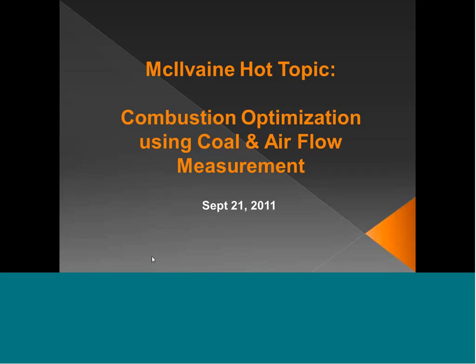Now, the other thing we can do is, if there's a relationship between slip and fineness, if I were to look at the primary air into a pulverizer and compare it to the average velocity, which we calculate automatically on one of our screens in our SCADA system, why can't I convert that into slip? It's possible that we don't need to add any additional hardware if we have accurate primary airflow. So we're doing further testing on that. But right now, the device that I showed is a separate device, and typically it goes in one pipe out of each mill.